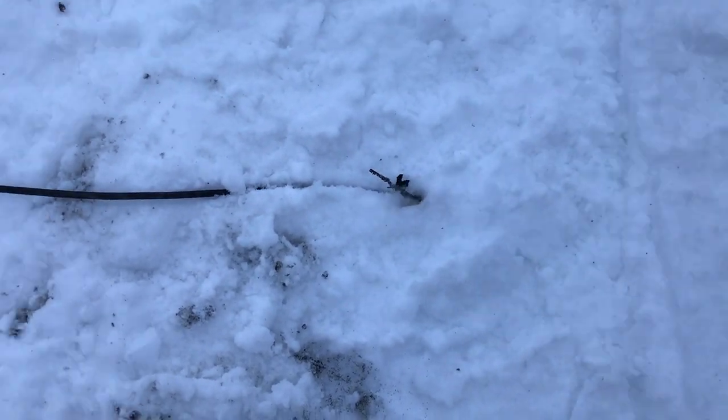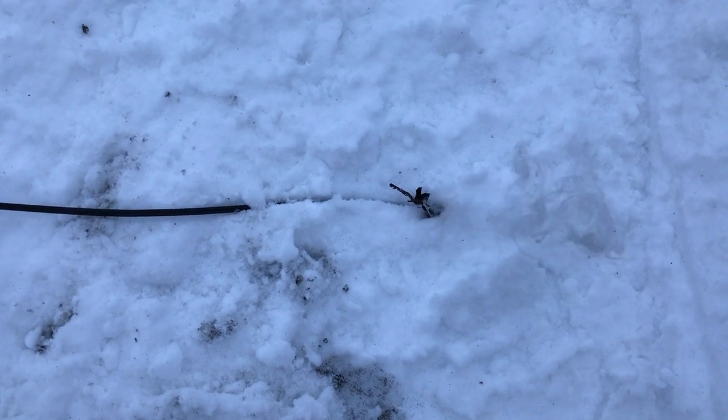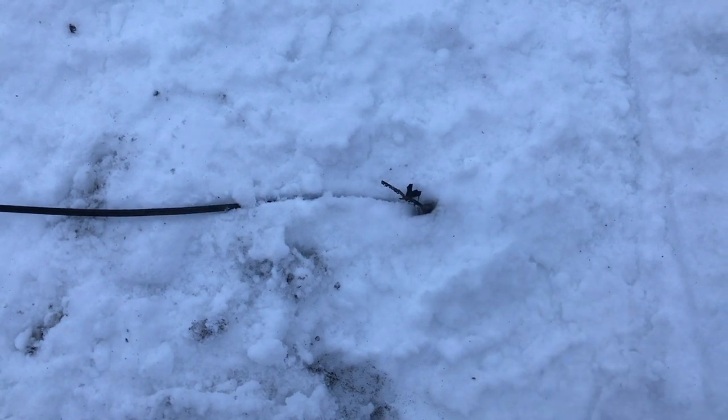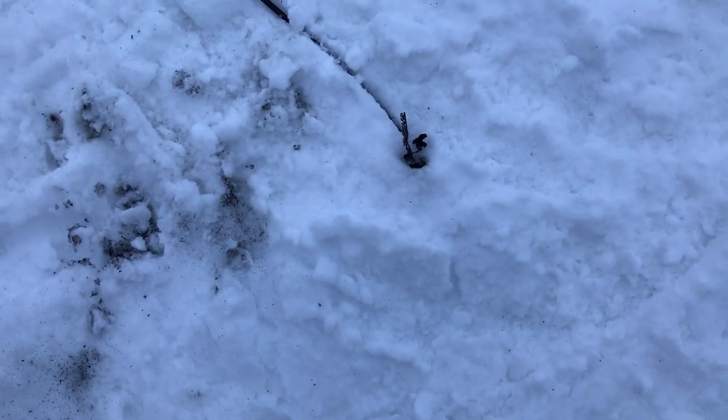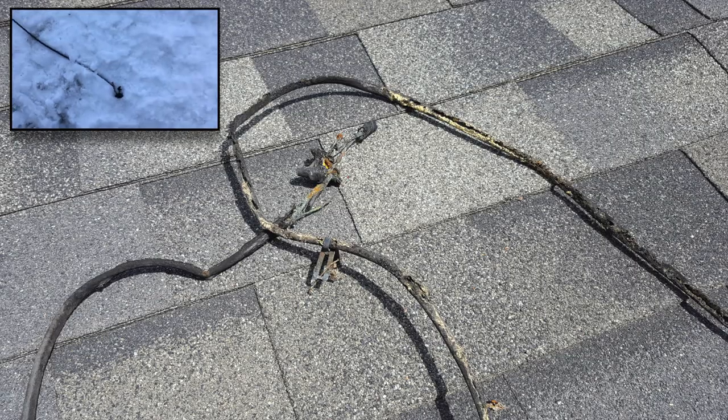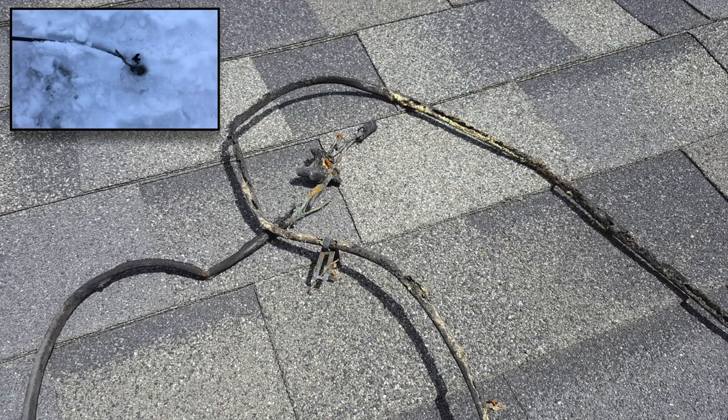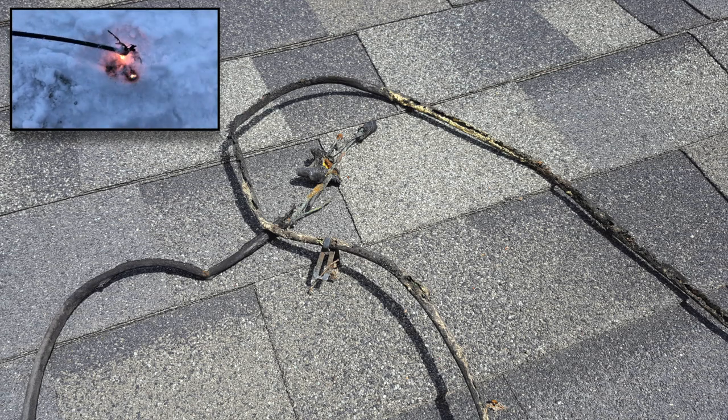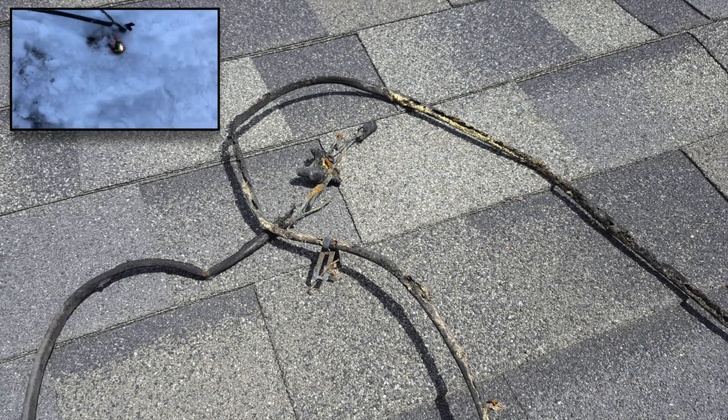The other interesting thing about this is the amount of cable it burned in a matter of three minutes. It only burned about five or six inches, but we have found cable on roofs that have been burned down seven, eight, nine feet, which would tell me they've been burning for a long period of time before something shut it off.